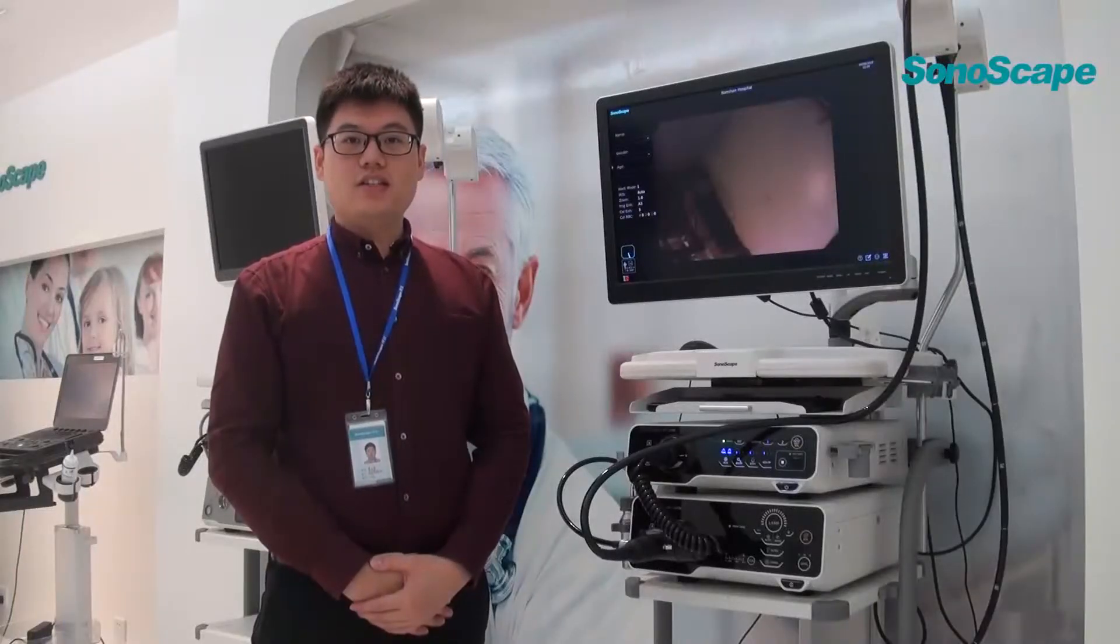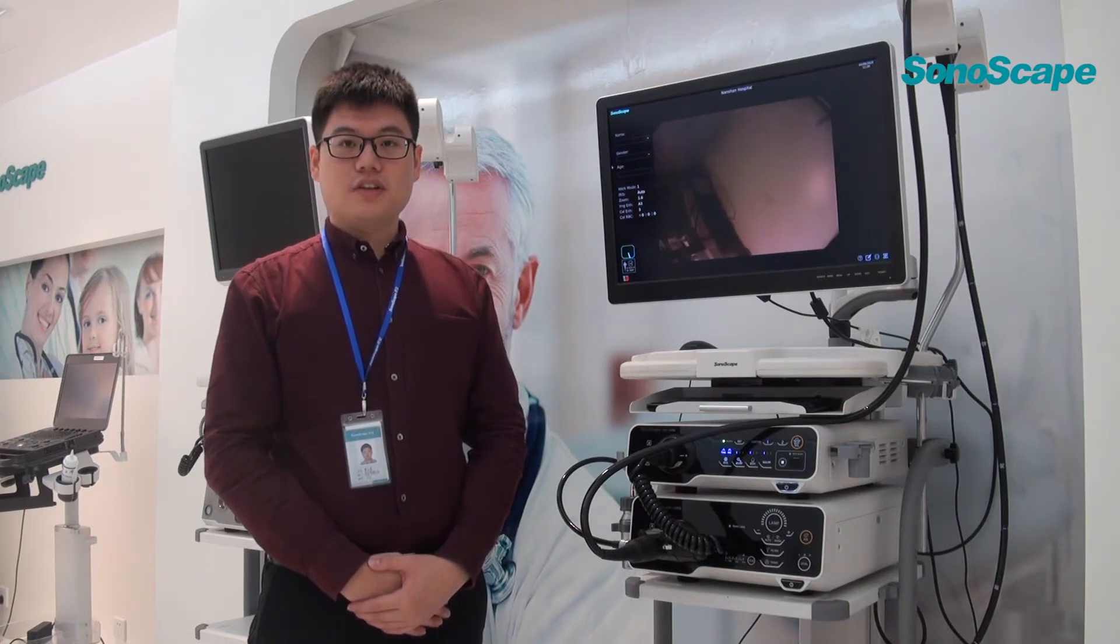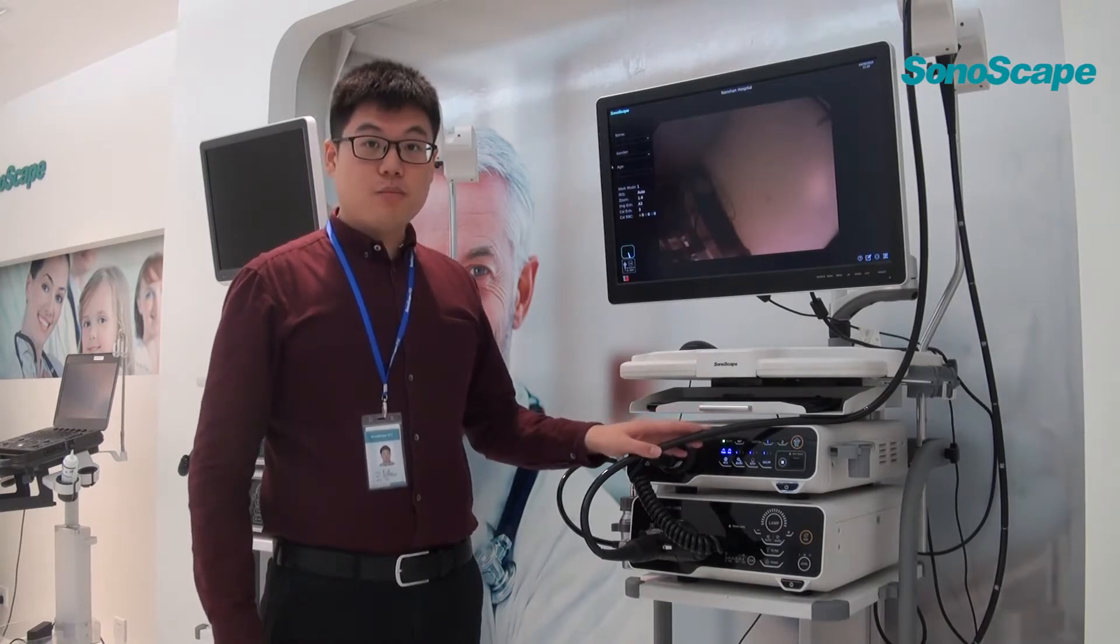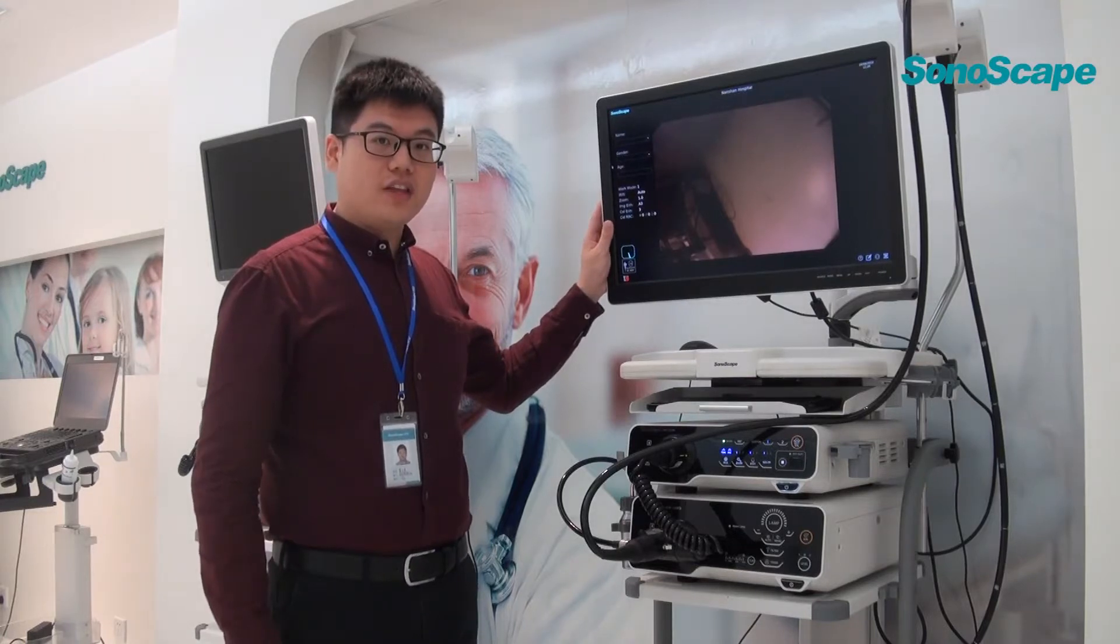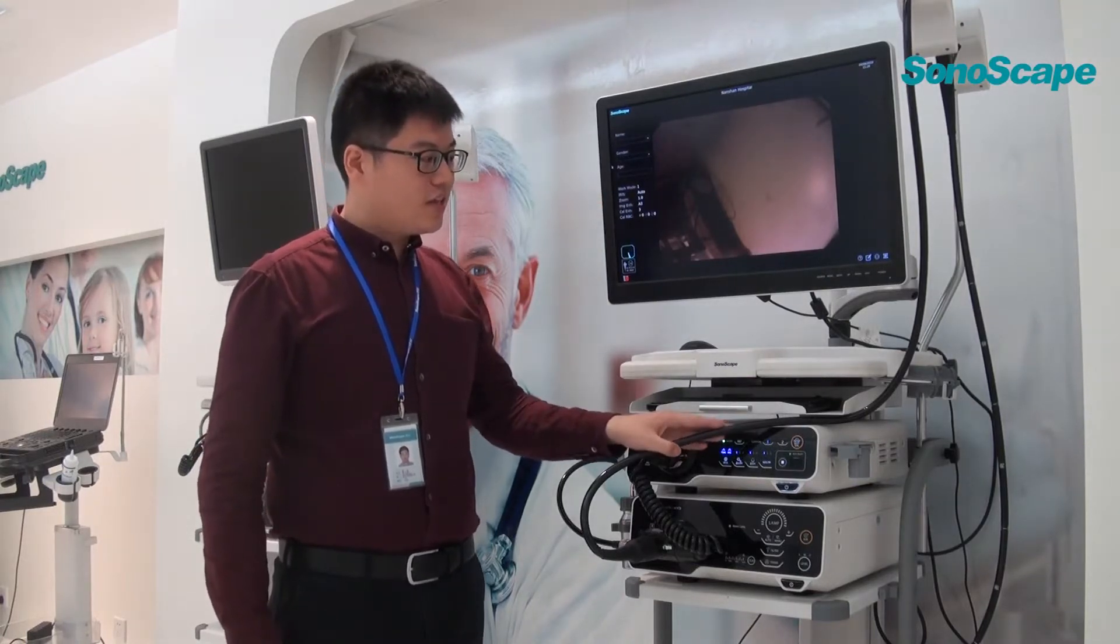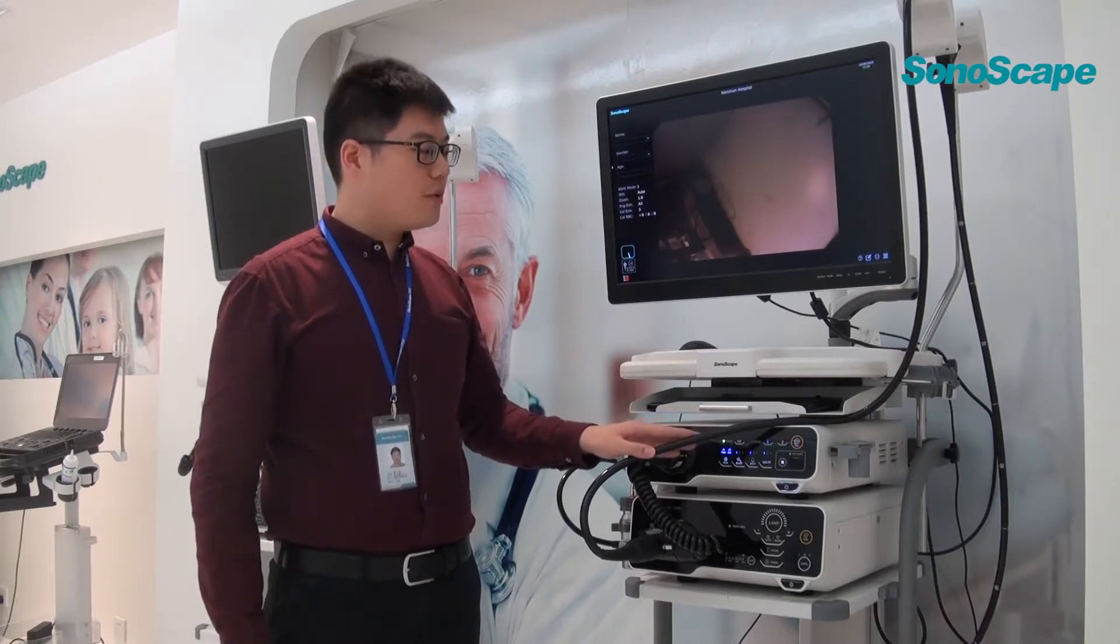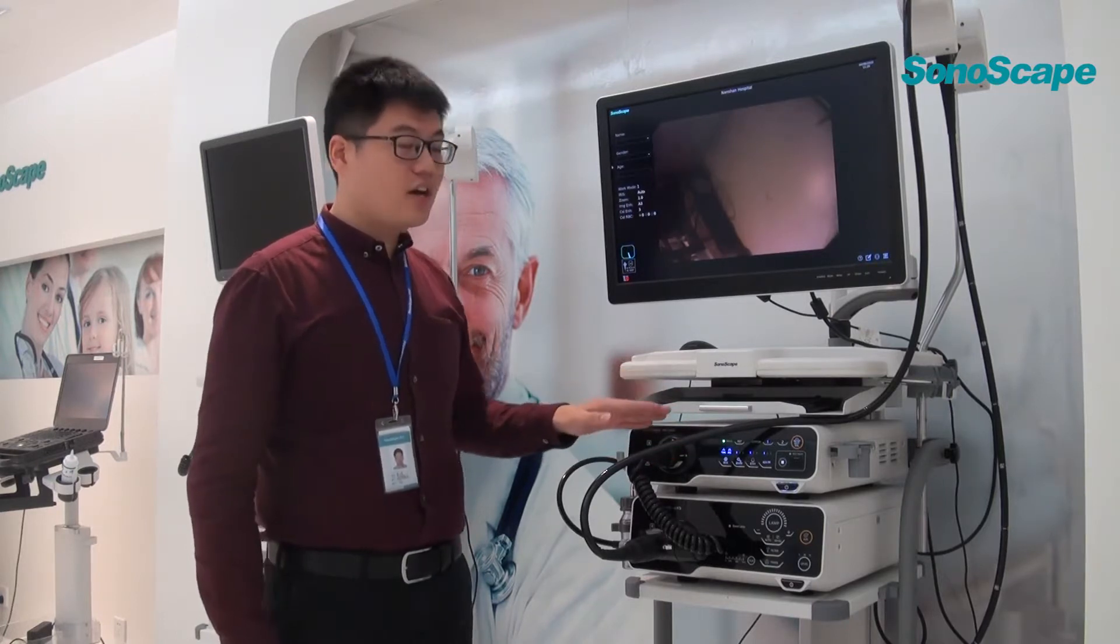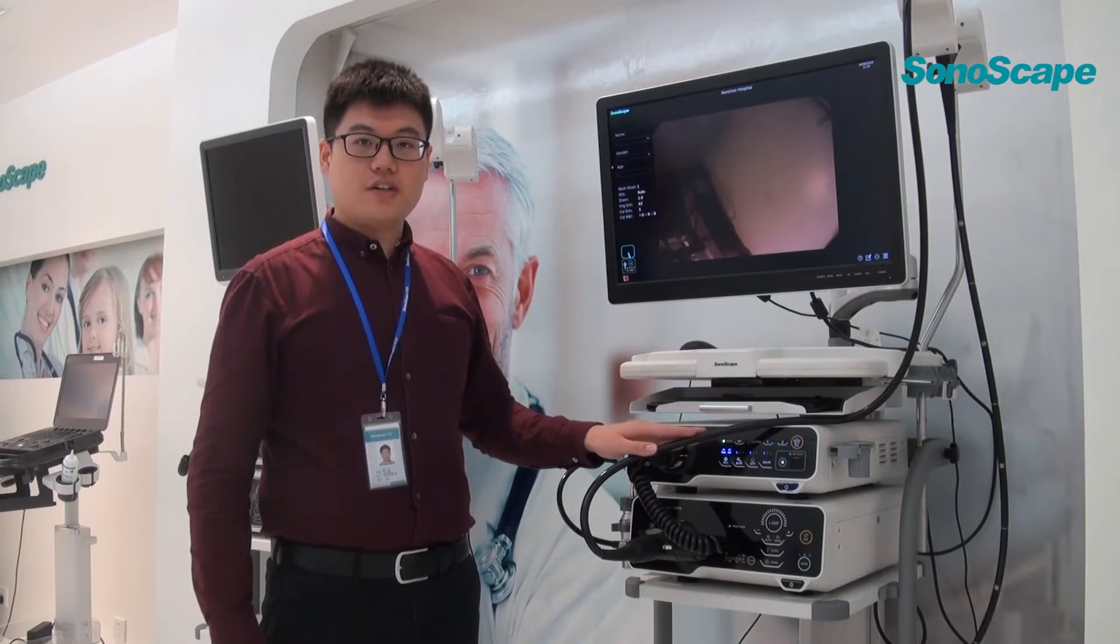Generally speaking, the HD500 system has three biggest features. At first, for the endoscope itself, it adopts high-definition CMOS technology to ensure the clarity and sharpness of the image. Six different sizes in working lens and instrument channel diameter can be well used for common diagnosis and therapeutics. All the GI endoscopes are with auxiliary water jet function.